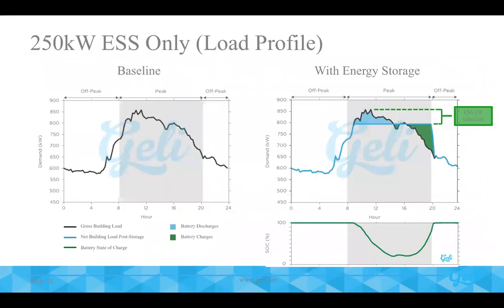All right, well, let's talk about energy storage alone. So again, here's this baseline graph. And on the right is what the effect of a 250 kilowatt energy storage system would be on that load profile. You'll notice that we've introduced a new little graph below the load profile on the right. That is the battery state of charge. And you can see that it goes from 100% almost down to 0% and then charges back up. In this case, over the course of the day, the battery is discharging to mitigate peak load and then recharging when the load subsides in the afternoon. And so the battery takes it from about 850 kilowatts to 800 kilowatts.